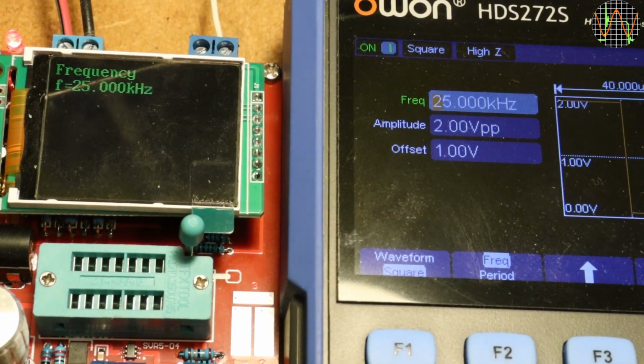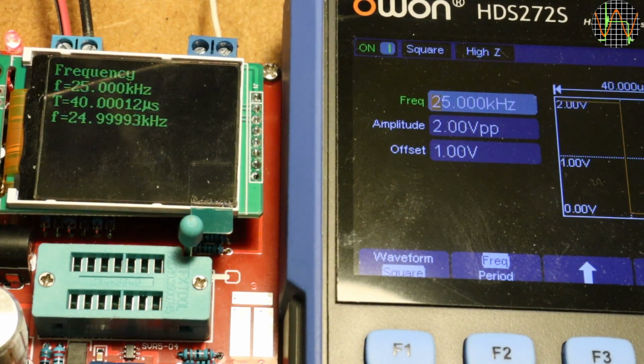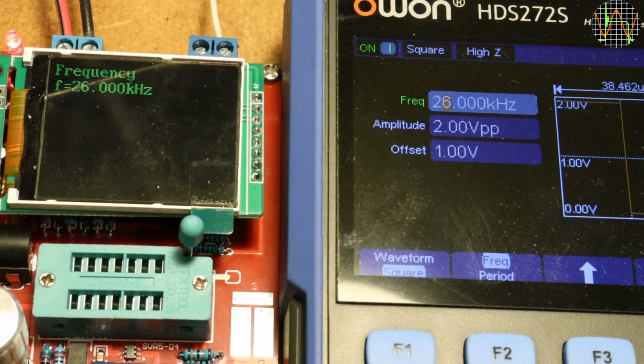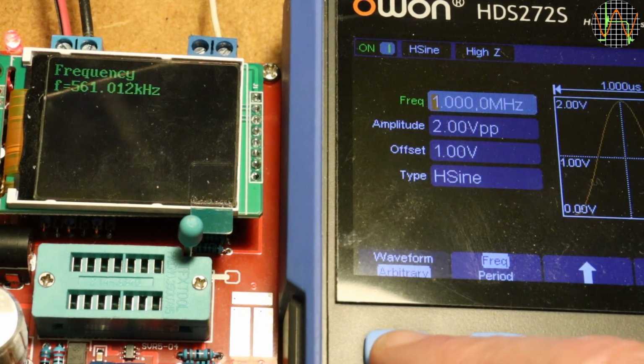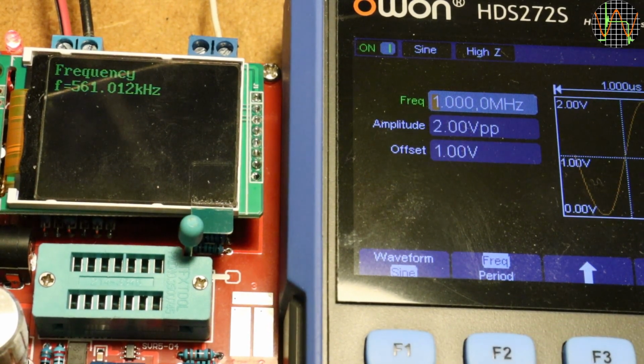25 kHz, this is the highest frequency with period measuring. 26 kHz, and from now on only frequency is measured. 50 kHz now. Half a megahertz, no problems. 1 megahertz. 2 megahertz is still fine. And so is 3 megahertz. But 4 megahertz is too much. Sine or square waveform is no problem, but 3 megahertz is the limit for this tester.